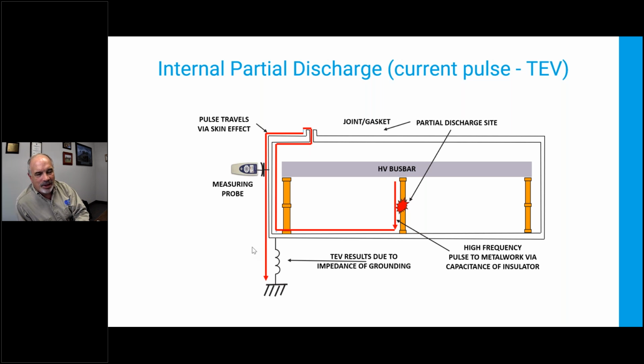It finds a path to ground, and that path to ground is the grounding of your switchgear arrangement or the ground strap on your cable or whatever it is. That's a great low impedance ground at 60 hertz. Damn near zero at 60 hertz. But at 60 megahertz, it's not so great. Big, thick bus bars are really bad RF ground sources. So what happens is we have a bit of an impedance. Now we go back to Ohm's law: I have a current across an impedance, I get a voltage.